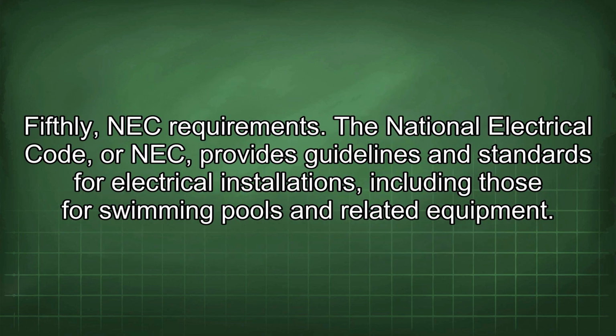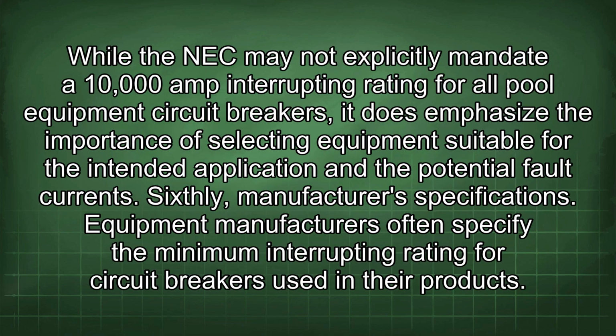Fifthly, NEC requirements. The National Electrical Code, or NEC, provides guidelines and standards for electrical installations, including those for swimming pools and related equipment. While the NEC may not explicitly mandate a 10,000 amp interrupting rating for all pool equipment circuit breakers, it does emphasize the importance of selecting equipment suitable for the intended application and the potential fault currents.